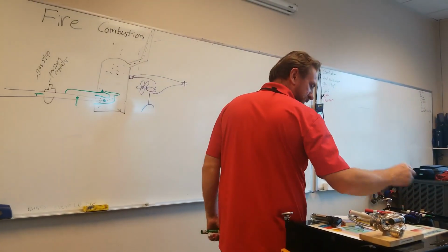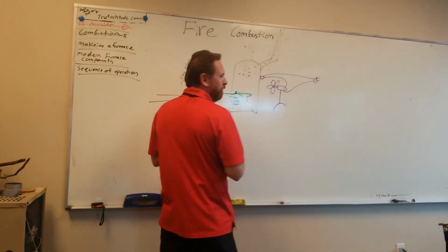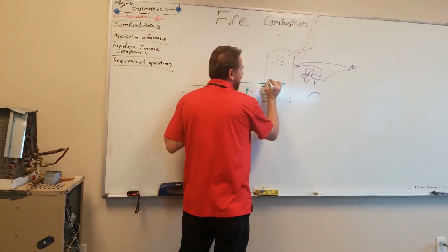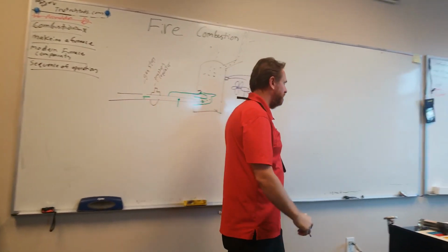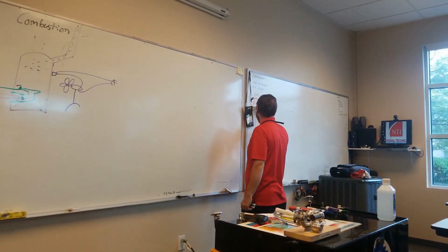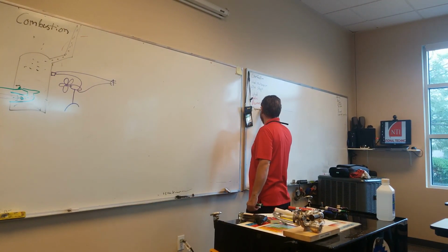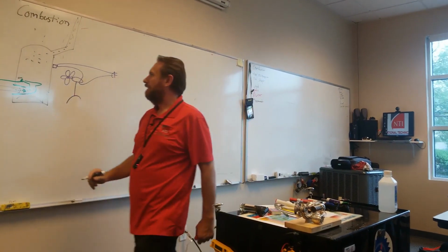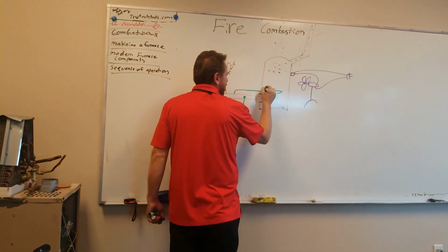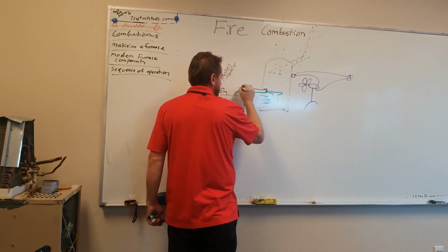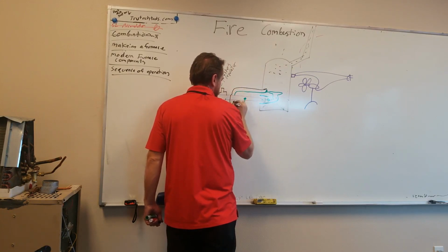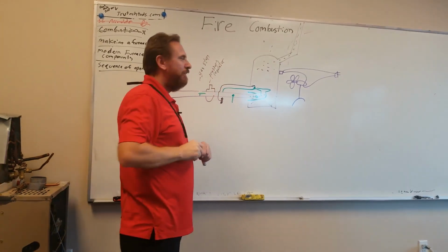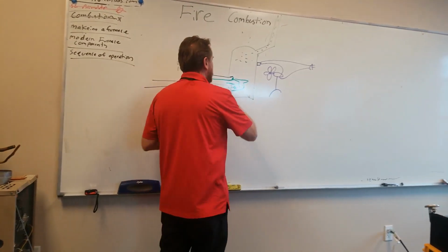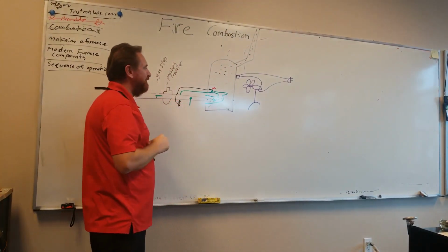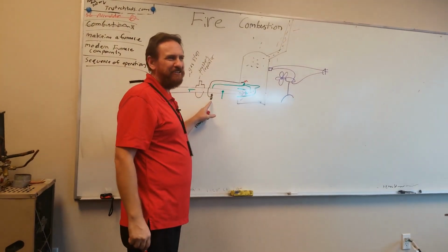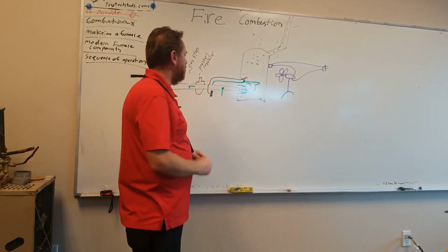So what we're going to do is include a component called a thermocouple. A thermocouple is a device that when heated creates current and voltage. It's a little device that the pilot is going to burn on. It's going to convert heat energy into electrical energy. So as that pilot light burns against this thermocouple, it creates heat energy. That heat energy creates an electromagnetic field that keeps this valve open right here before it.